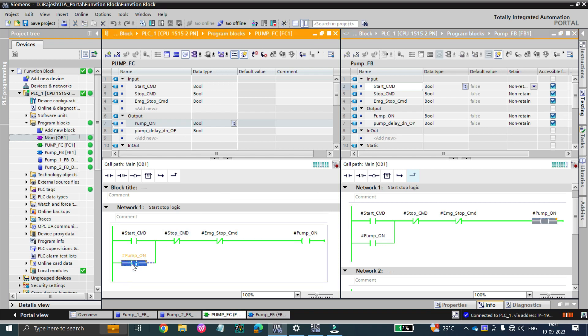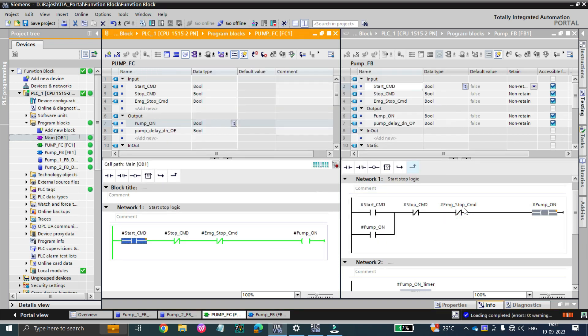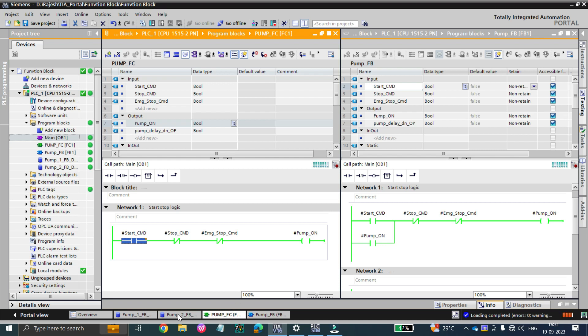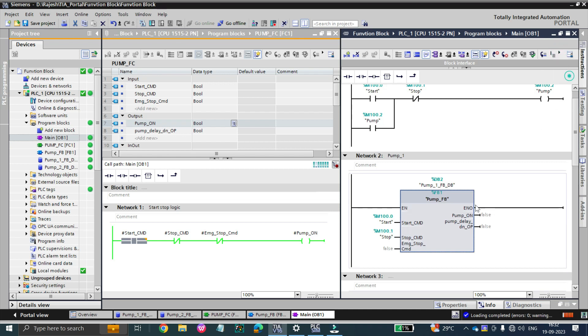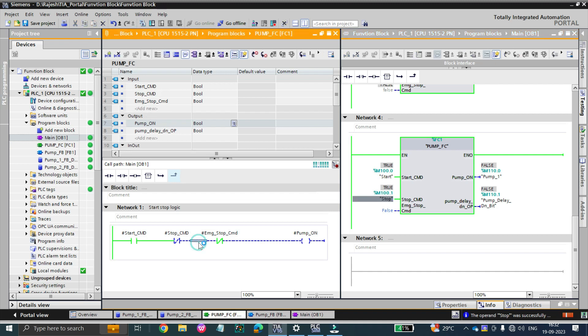This is the basic difference between function block and function. A function can only do logic — for example, if we don't have this pump-on latching requirement, it will work fine. Currently what's happening: the pump turns on and when we stop it, it will stop — no problem. But if you are using local tags in a function you are limited to this kind of logic. If you are accessing global tags then the function is fine, but using local tags introduces project limitations.